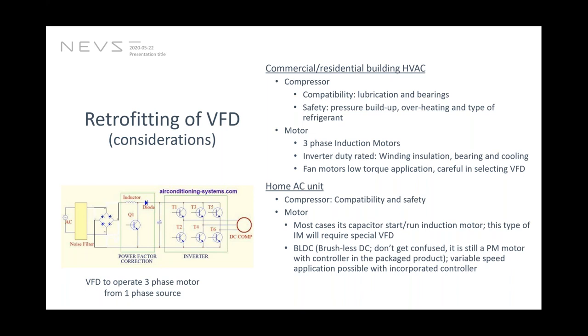But in our part of the world, in South Asia, residential buildings are small, not big residential buildings, and lack a centralized HVAC system. So we have a home AC unit. I would like to compare that as well. Is it possible to retrofit a VFD into the conventional one? In the residential building, there are two things to look at. Is our compressor compatible with a variable speed application, especially with lubrication and bearings? And is the compressor safe with regard to pressure buildup and overheating?